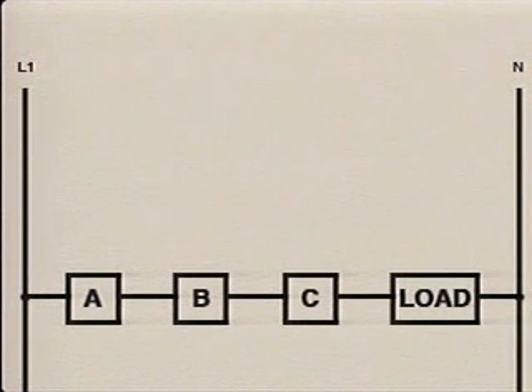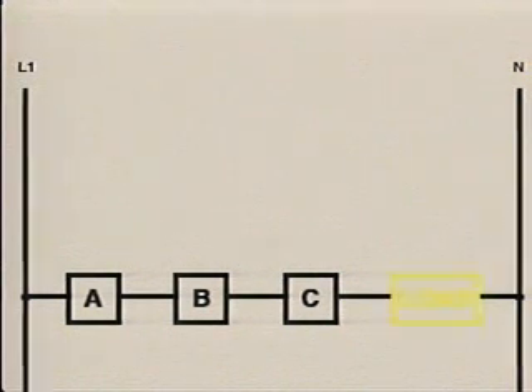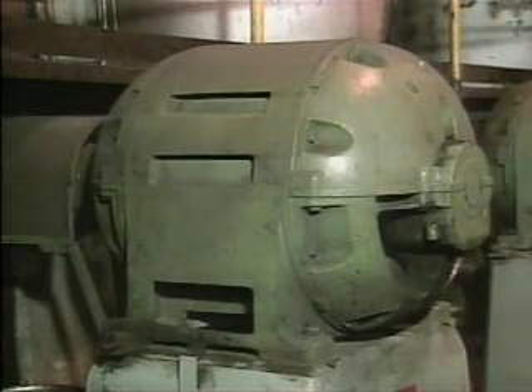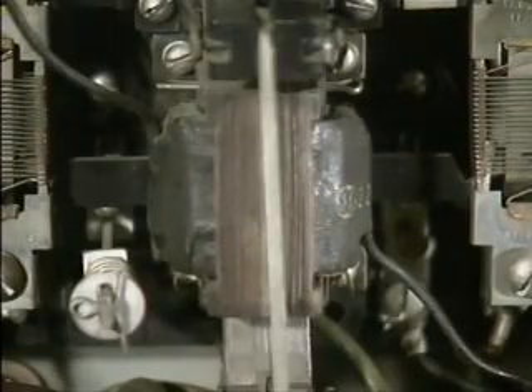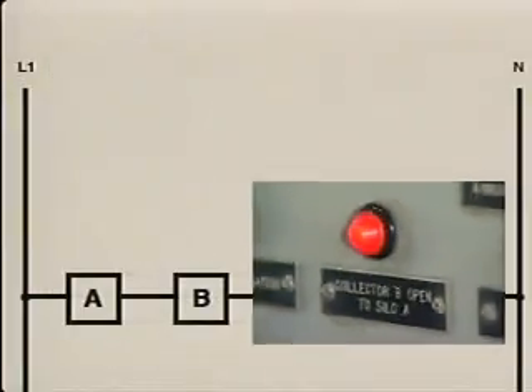We can see how making voltage checks can eliminate possible causes of a problem by using this illustration, which represents the control circuit for a piece of electrical equipment. This illustration contains 4 blocks. The block on the right represents the circuit's load, which uses electrical power to do work. Common examples of a load include motors, control relays, and lights.